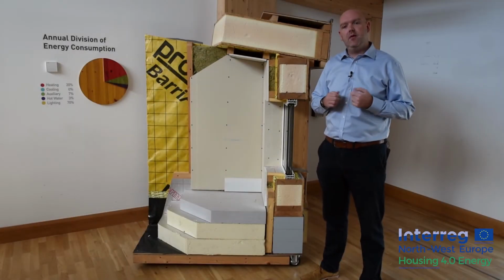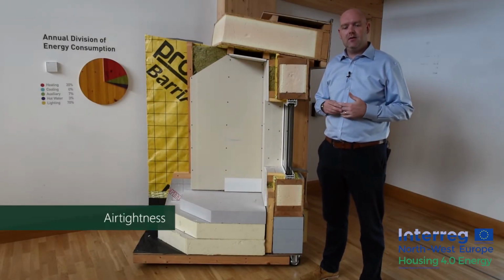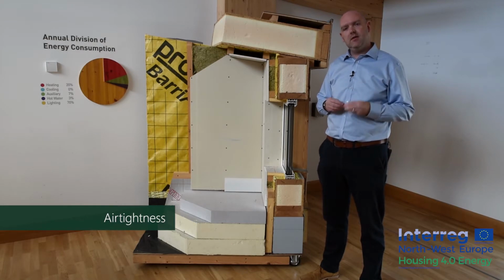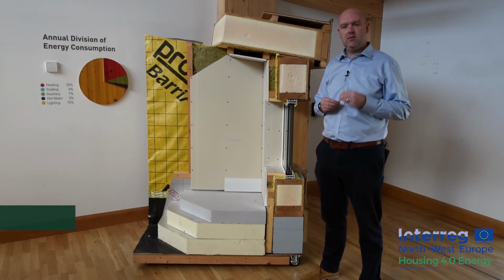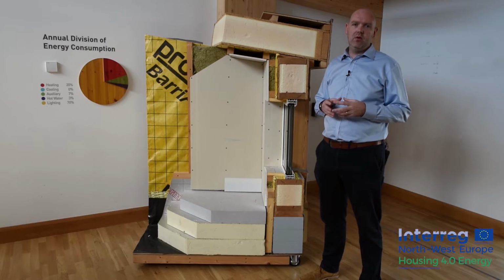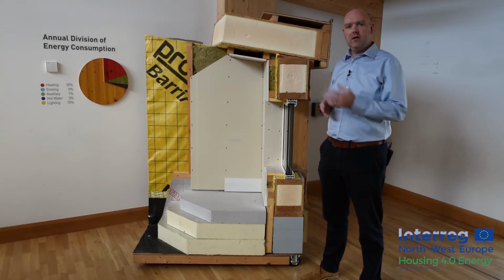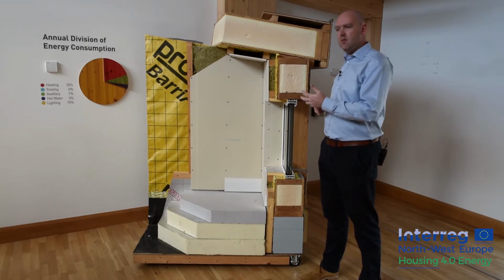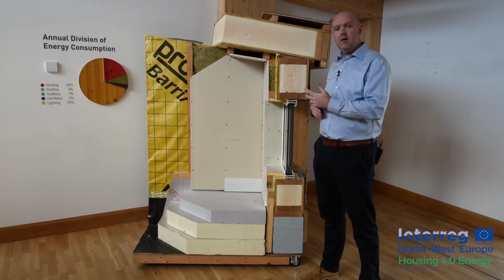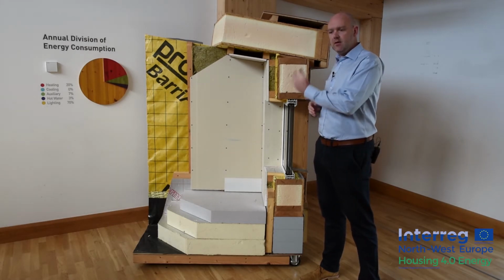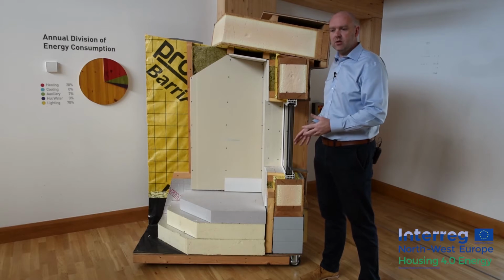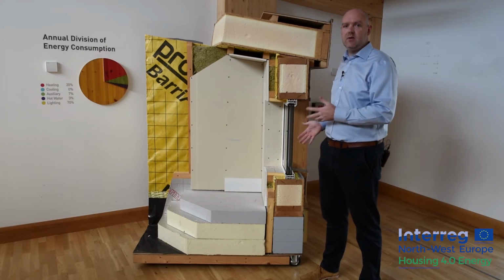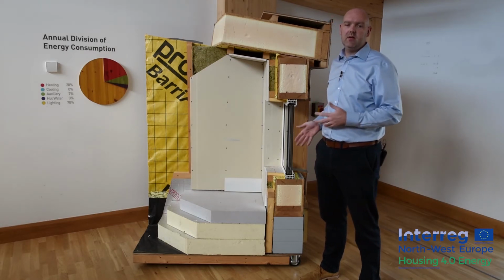The fourth principle of the passive house standard is air tightness. The criteria for air tightness is 0.6 air changes per hour as tested by a blower door at 50 pascals. We can see here in this cutout, as is timber frame, where we have the air tightness detailing and the air tightness membrane and taping at various junctions. This is very typical for a timber frame construction built to the passive house standard.